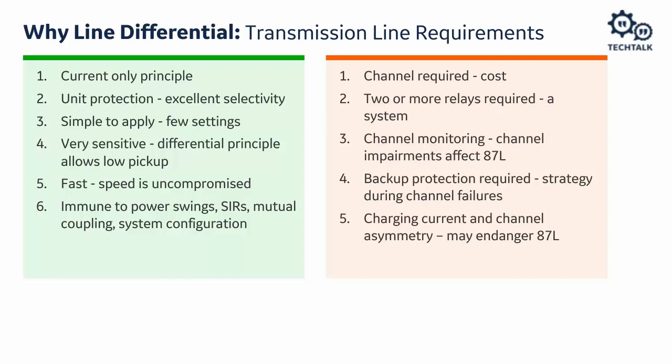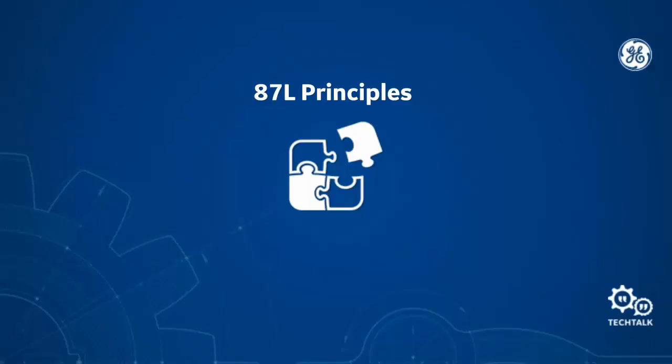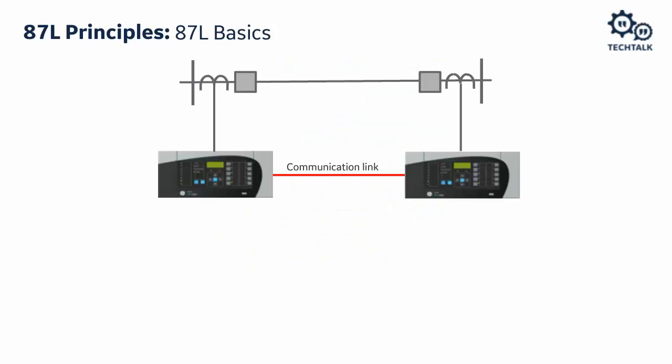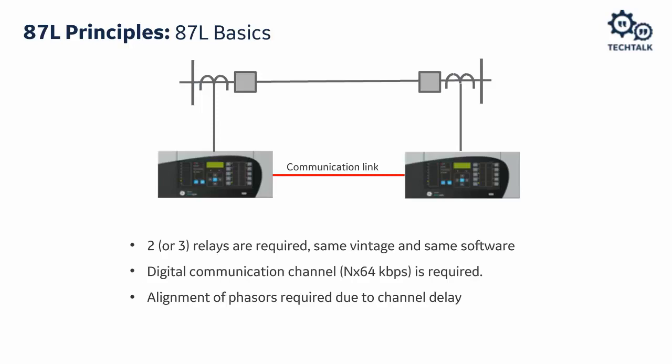The system has two relays connected with a communication link and CTs at both ends of the line — this makes our zone of 87L protection. We need two relays for a two-terminal line or three relays for a three-terminal line.